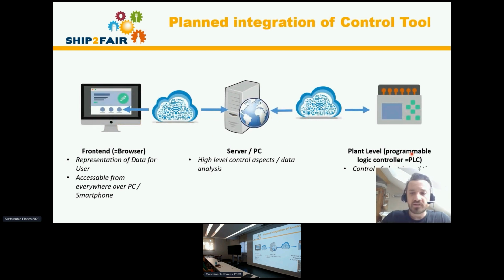The typical structure is that we have a programmable logic controller, a PLC, on site at the plant. Then we have an internet connection to a server or PC where the high-level control aspects are calculated, and furthermore an internet connection to a front end, just a browser like Chrome, Firefox or Edge, where you can access these control modules. Modules A and B, controlling the solar thermal plant and the hydraulic integration, have to be implemented on the PLC since they must run in real time.